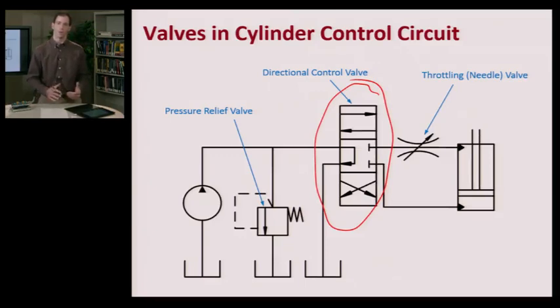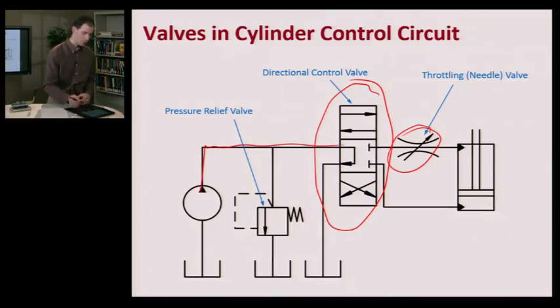When we started to control the velocity of the hydraulic cylinder, that's when we used this throttling or needle valve right here. The purpose of this was to restrict the flow. What was happening is we were building up pressure upstream of this valve, from the outlet of the pump through the directional control valve to the inlet of this pressure relief valve.